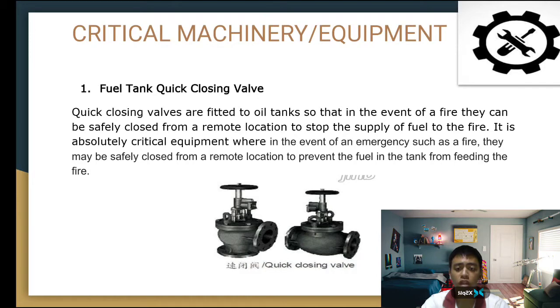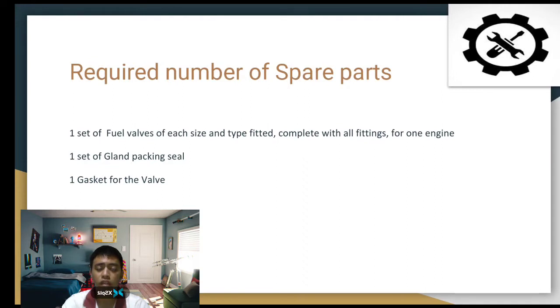As we all know, this fuel tank quick closing valve can help to prevent an event such as fire, because the flow of this valve is fuel, and we all know that fuel is one of the elements of the fire triangle which can create fire. The triangle consists of fuel, oxygen, and heat. The required number of spare parts of a fuel tank quick closing valve is one set of valves of each size and type fitted, complete with all fittings for one engine, one set of gland packing seal, and one gasket for the valve.